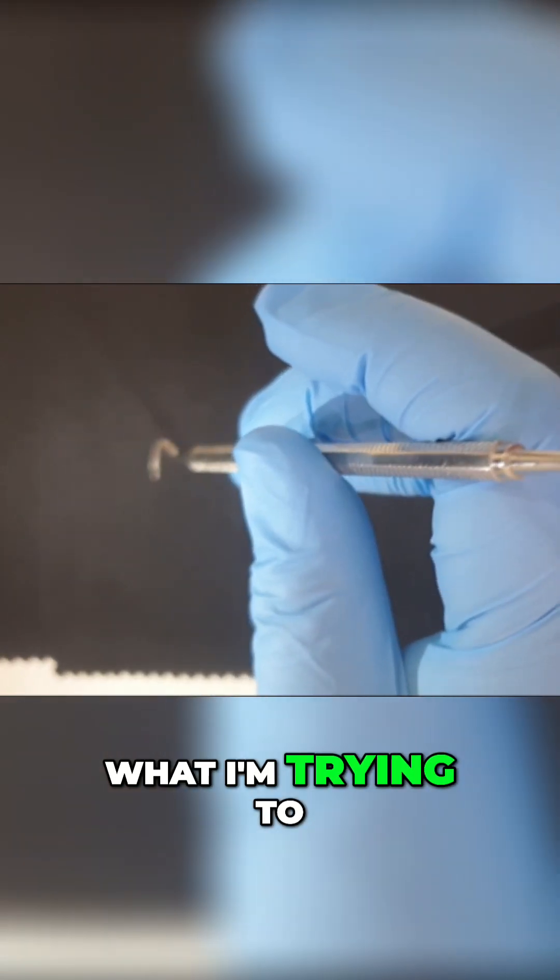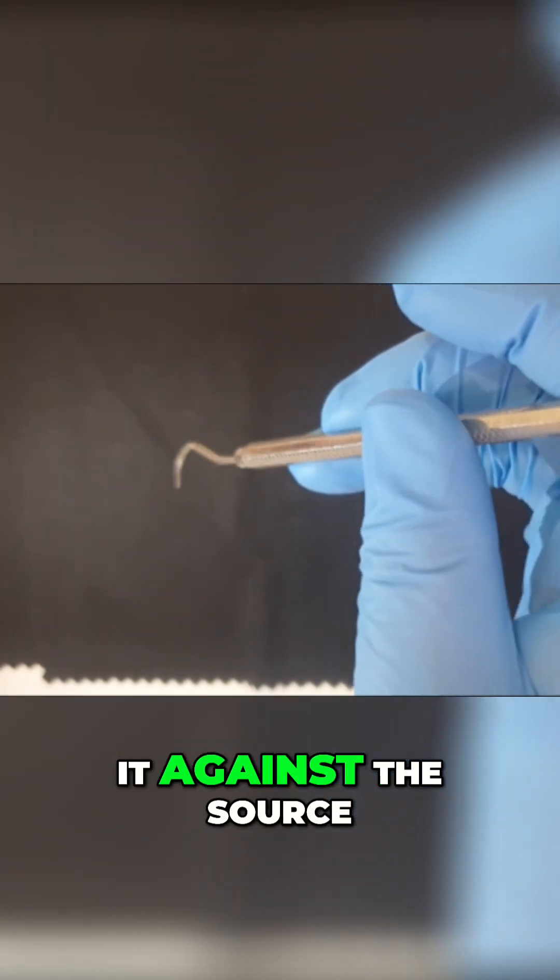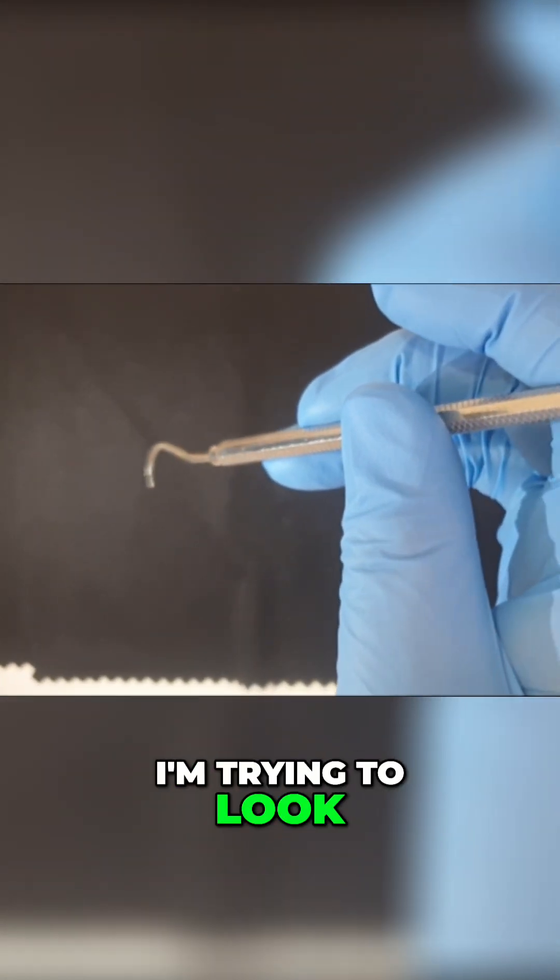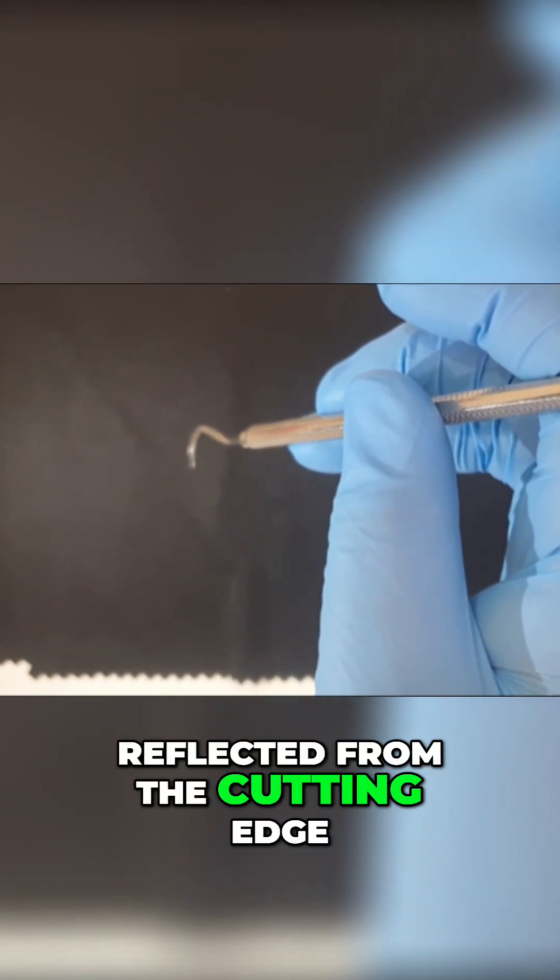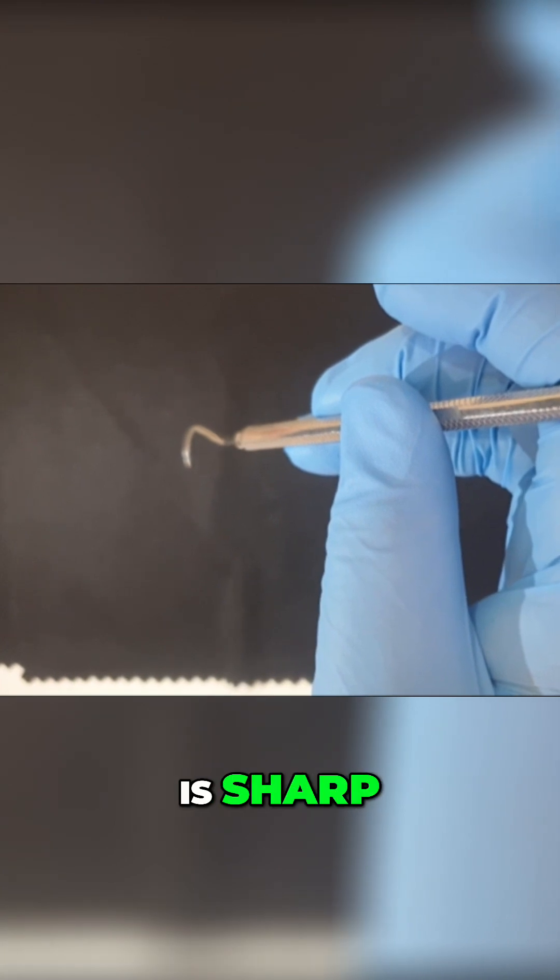Now what I'm trying to do is hold it against the source of light. I'm looking at the cutting edge. I am not able to see any light being reflected from the cutting edge. That means my instrument is sharp.